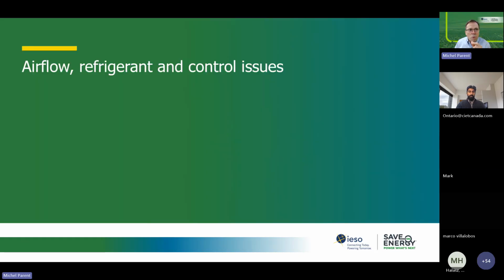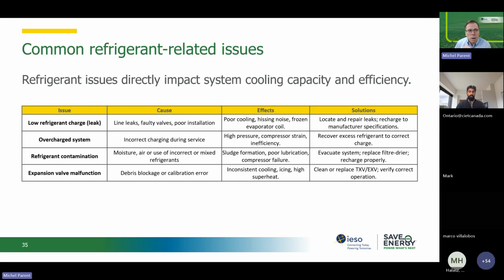Quick words about the refrigerant and airflow. We already talked a bit about refrigerant and also a bit about airflow. This is not exactly like electrical, where you always call an electrician because you should never take the risk of working on electrical. On the refrigerant side, you will unlikely do any work that requires actually going into a system, recharging the system. This is very specialized work that will be done by the refrigeration technician. But you should be able to diagnose the most likely reason for an issue.